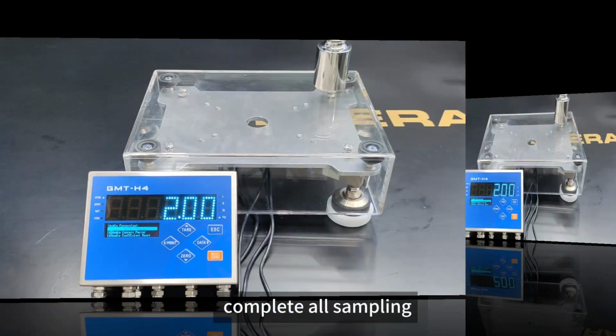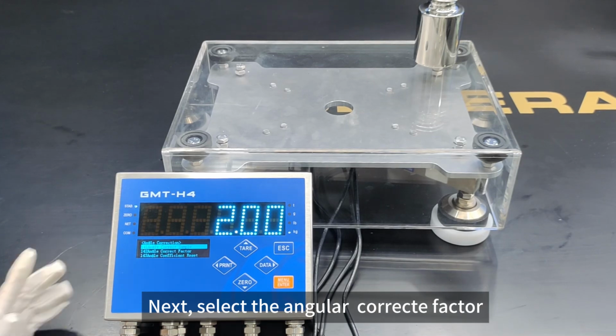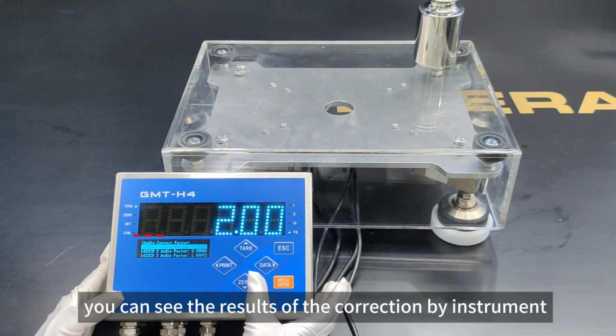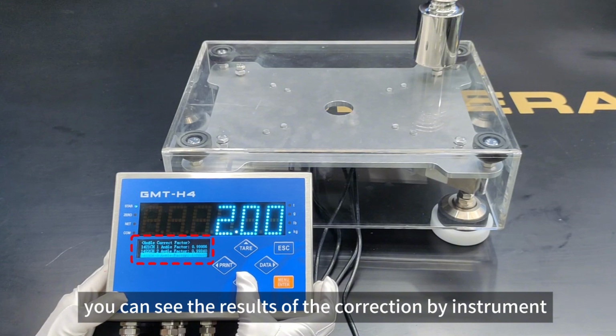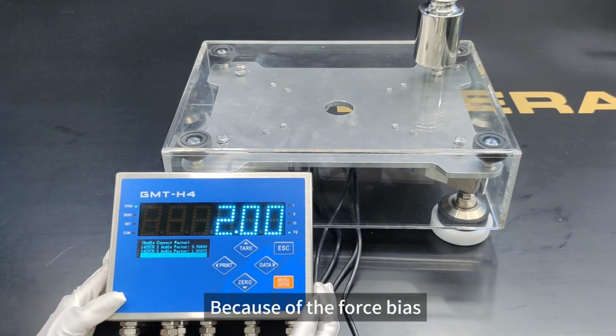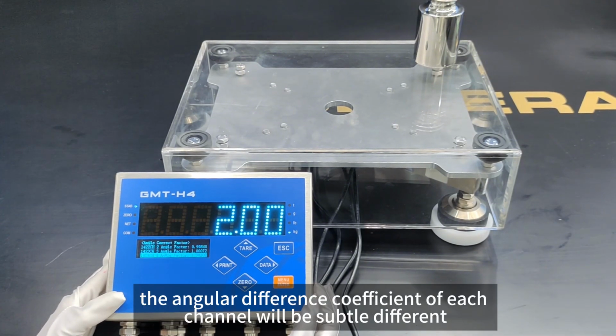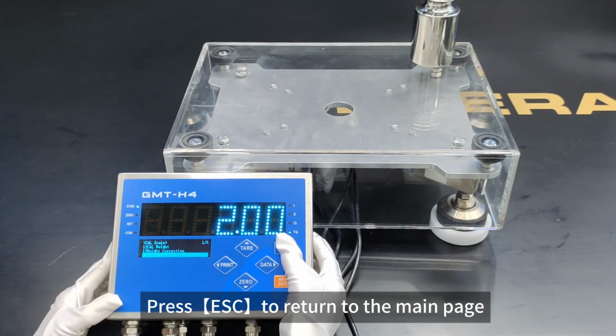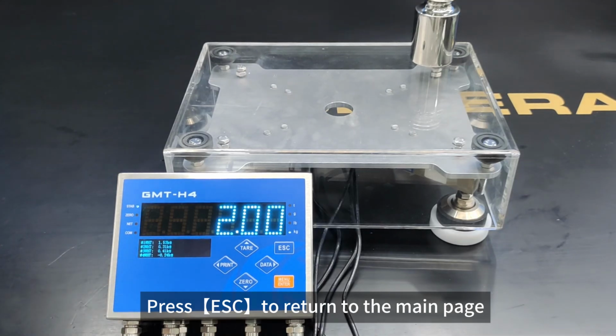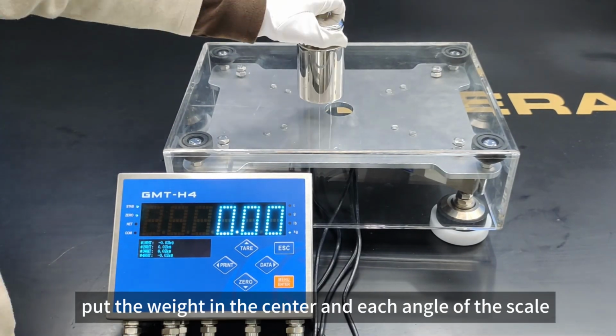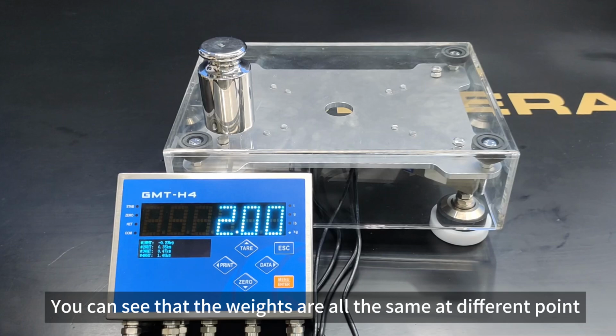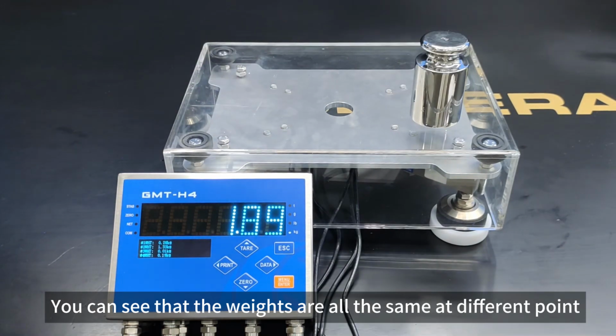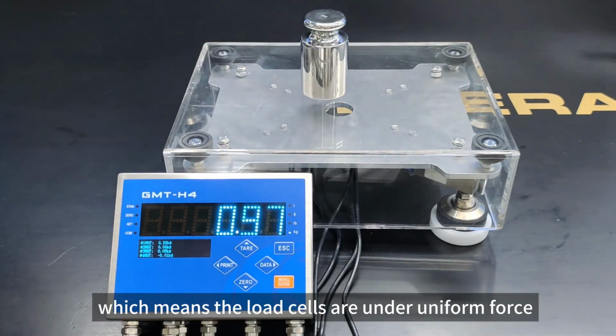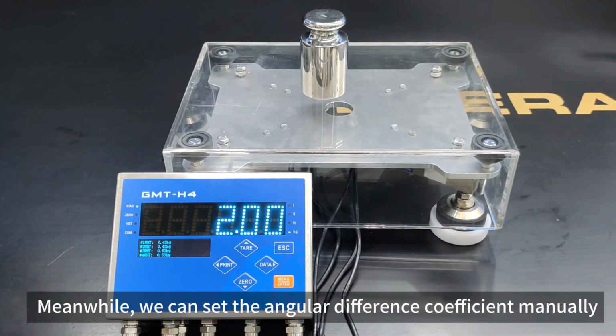Complete all sampling. Next, select the angular correct factor. You can see the results of the correction by the instrument. Because of the force bias, the angular difference coefficient of each channel will be subtly different. Press ESC to return to the main page. Put the weight in the center and each angle of the scale. You can see that the weights are all the same at different points, which means the load cells are under uniform force.